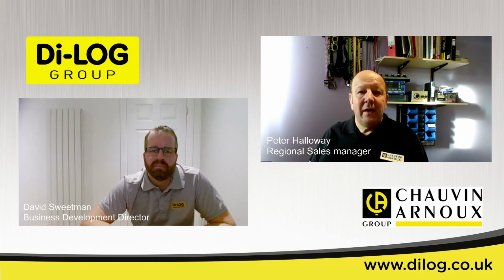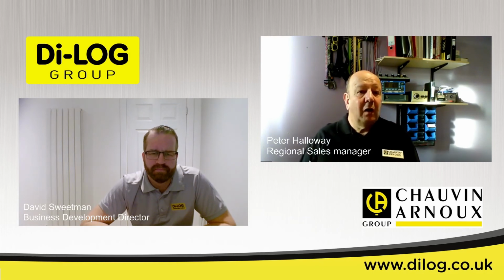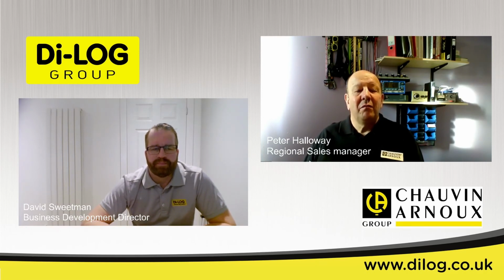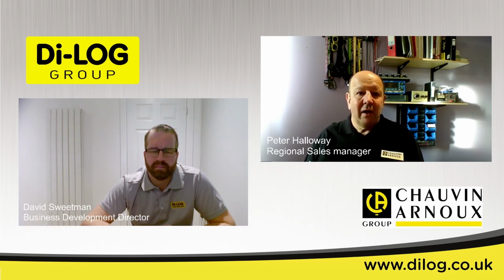Going on to the second part of the question, power factor getting worse over time - I'd probably ask if they've got power factor correction, and we can perhaps touch on that, if not today, on another occasion. Effectively, power factor correction is a bank of capacitors put in parallel with the load to counteract that inductive load to help with the power factor, hence power factor correction.